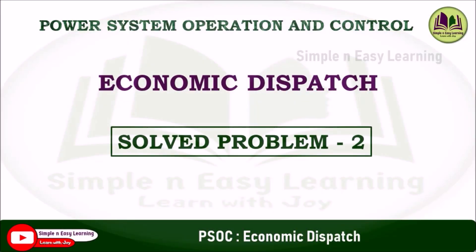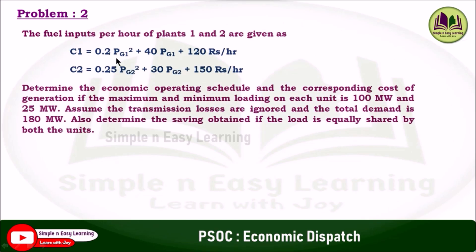Economic dispatch solved problem 2. In the exam point of view this problem is very important. The fuel input per hour of plant 1 and plant 2 are given as C1 equal to 0.2 PG1 square plus 40 PG1 plus 120 rupees per hour, and C2 is 0.25 PG2 square plus 30 PG2 plus 150 rupees per hour. Determine the economic operating schedule and the corresponding cost of generation if the maximum and minimum loading on each unit is 100 megawatt and 25 megawatt. Assume transmission losses are ignored and the total demand is 180 megawatt. Also determine the saving obtained if the load is equally shared by both the units.